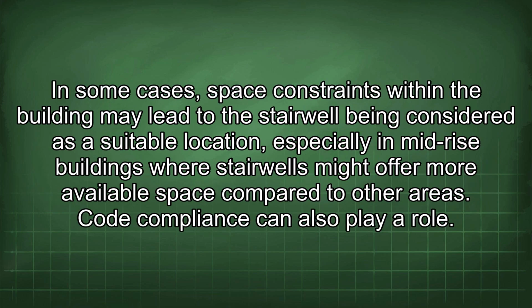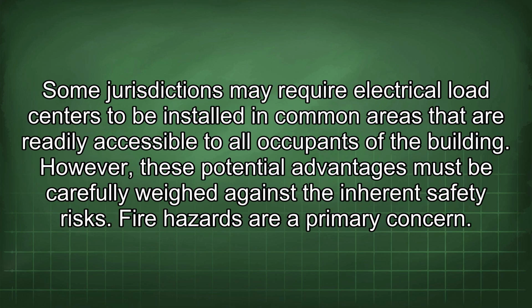In some cases, space constraints within the building may lead to the stairwell being considered as a suitable location, especially in mid-rise buildings where stairwells might offer more available space compared to other areas. Code compliance can also play a role. Some jurisdictions may require electrical load centers to be installed in common areas that are readily accessible to all occupants of the building. However, these potential advantages must be carefully weighed against the inherent safety risks.